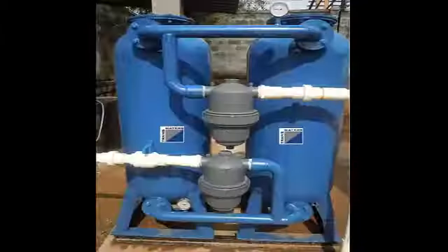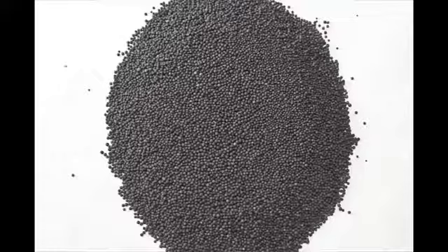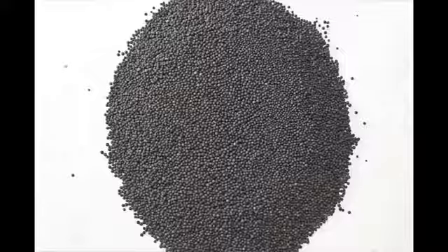If you only have two cylinders, one could be a multi-grade filter and the other a softener. People mix sand and carbon in the first cylinder, putting them in stage by stage based on the grading, and the second one can be the softener. If you have iron, people have an additional cylinder to remove dissolved iron from the water, using different manganese dioxide based material to treat iron. So if you live in an apartment complex, you have multiple stage cylinders.